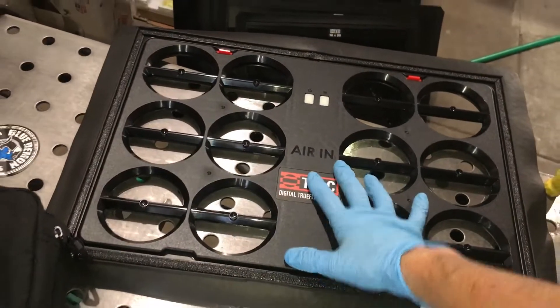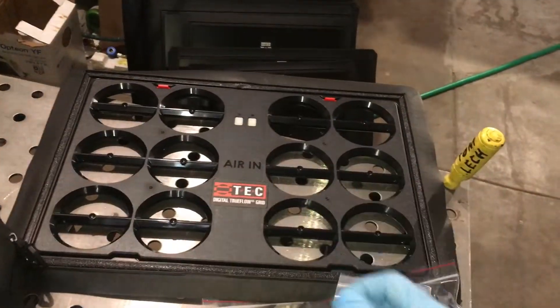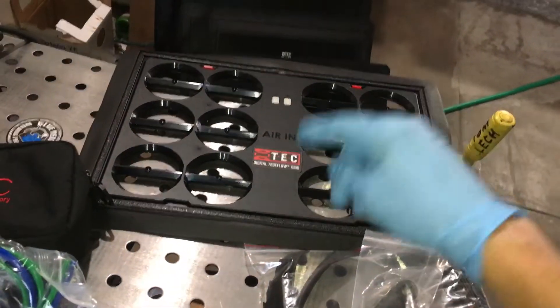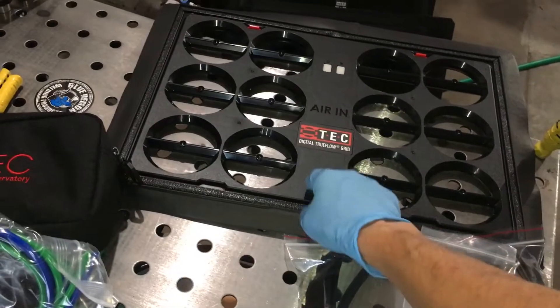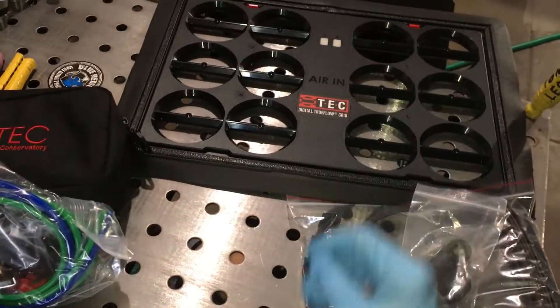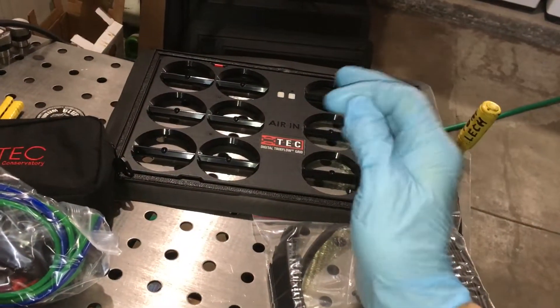You'll find this will be much more convenient than using pitot tubes or your vane anemometer readings. When I was at Laney College, we did traversing — we actually had to use the vane anemometer for the students to learn. They had the first one but weren't using it yet. This will dial in your airflow so you can accurately measure it. With vane anemometers, hot wires, or pitot tubes doing traverses, new and old technicians alike will all get different results.